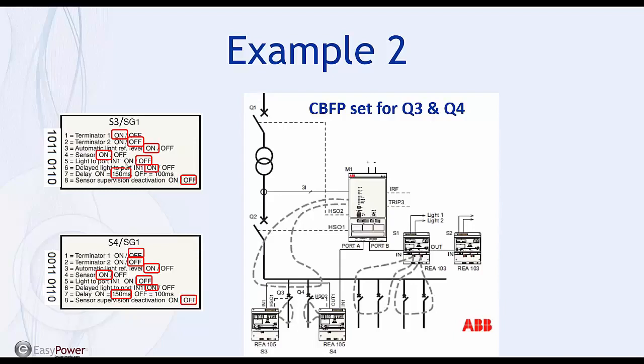You're activating your sensors. Light to port input 1 is off, so we don't want to send light back to the main unit. We want selectivity. That switch is, for all practical purposes, always off when you're using the REA105. And you have a delay of light back to the main unit of 150 milliseconds in the event that you have a breaker failure on either one of these feeders, either Q3 or Q4.